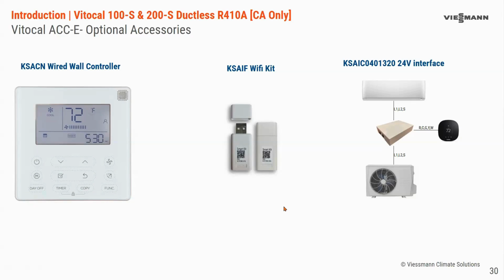We have the Wi-Fi kits. There are 2 models of Wi-Fi kit depending on which indoor unit you're selecting. And then there's the 24-volt interface, which acts as an intermediary between the outdoor and the indoor unit to allow you to power and have control by a 24-volt thermostat. In this case, the example is an Ecobee. And you would need one of these 24-volt interfaces at every indoor unit that you would want to have a thermostat. Compatible with single or multi-zone, all of these.